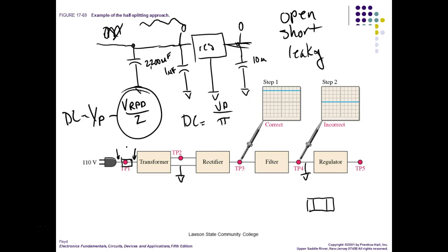The AC power's got a problem, right? If I measure 0 on my output side and 120 or whatever volts on the input side, it means the fuse is blown. If I measure the same on both sides, then what does that mean? That means it's good. The fuse is good. If you measure the same thing on what? Both sides. Everybody understand that? So you can check the fuse.